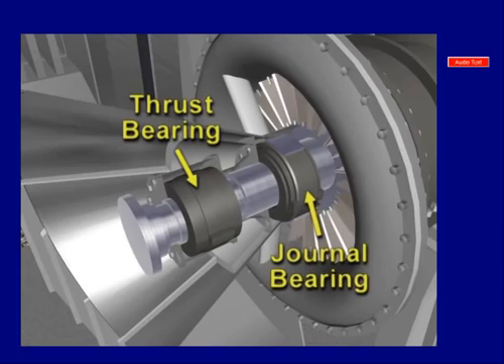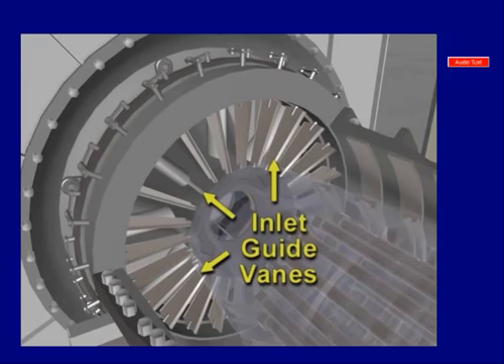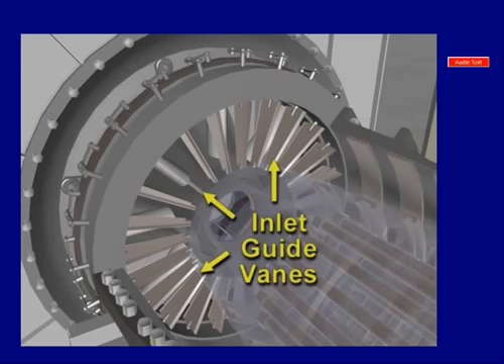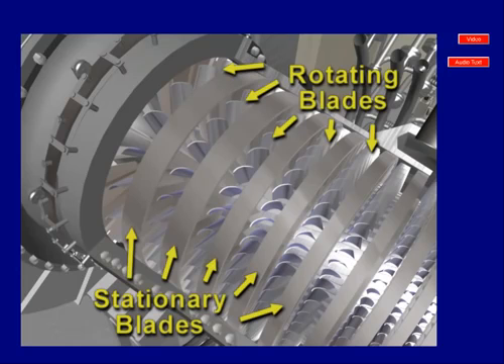The inlet casing also provides access to the thrust bearing and the inlet journal bearing. Variable inlet guide vanes are located in the inlet casing directly in front of the first row of compressor blades. The vanes are used to regulate the amount of air entering the compressor.